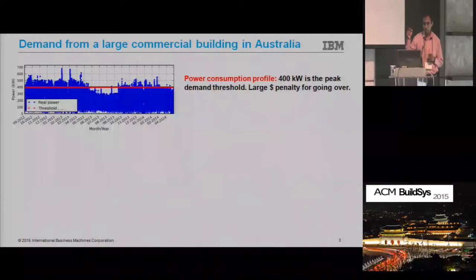Each blue dot records the power consumption at a 5-minute interval, and the red horizontal line is the demand threshold. This particular building has a 400 kilowatt peak demand threshold, so as long as you stay under 400 kilowatts you're okay. But the moment you exceed that for even a fraction of time—in this case a 5-minute resolution—you're penalized for that peak demand for the whole billing period. So there's a lot of incentive for this building to stay under the red line.